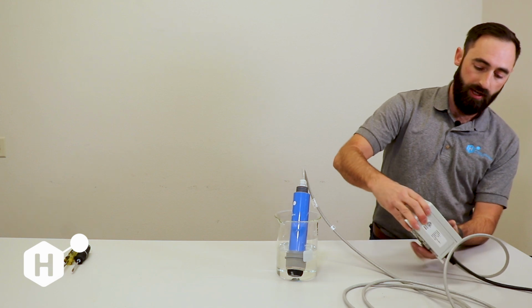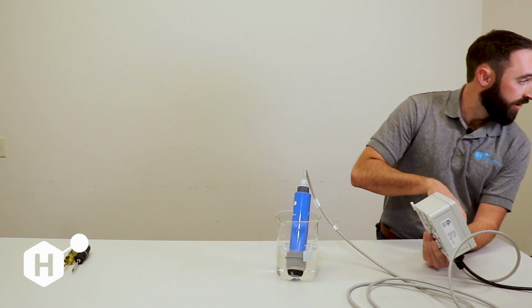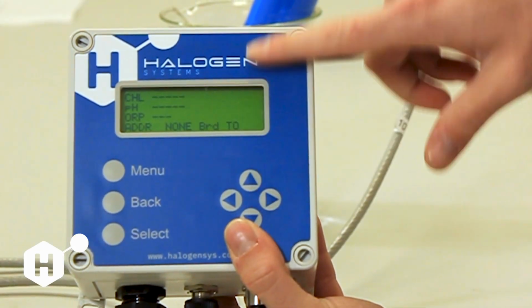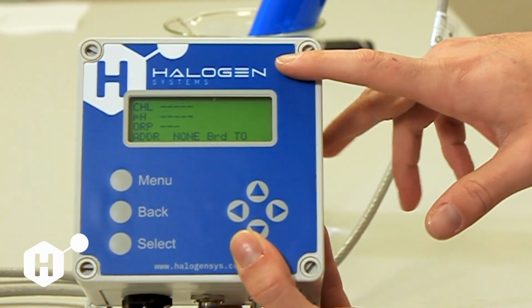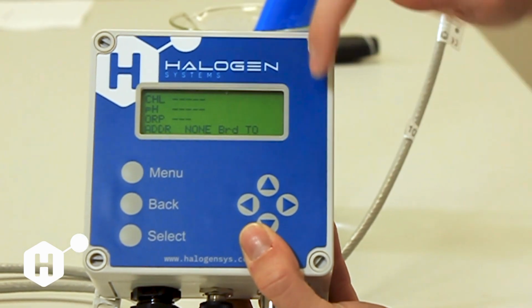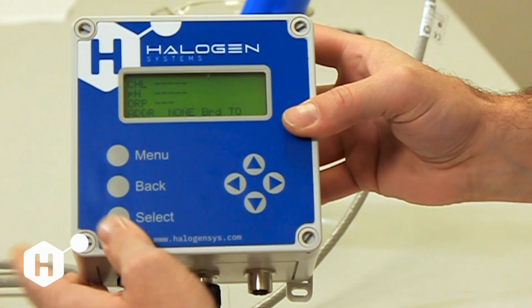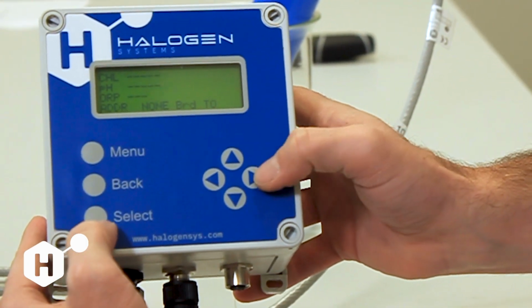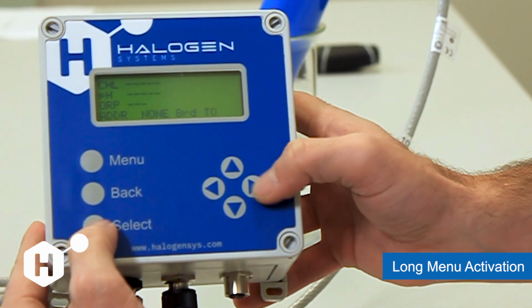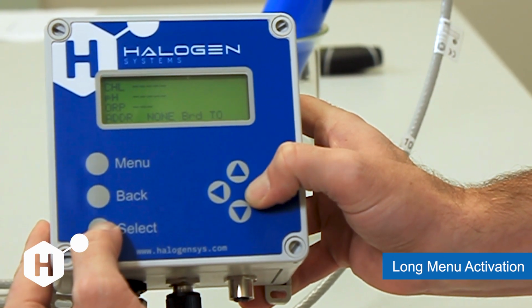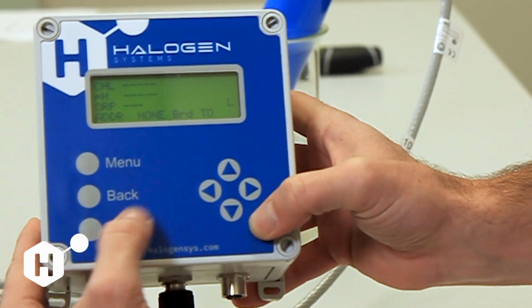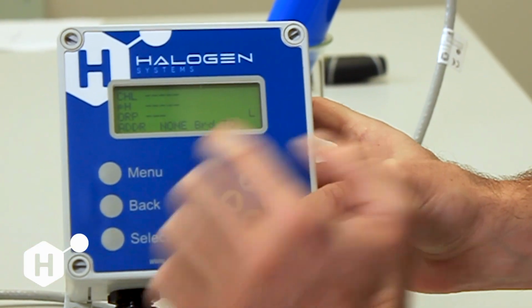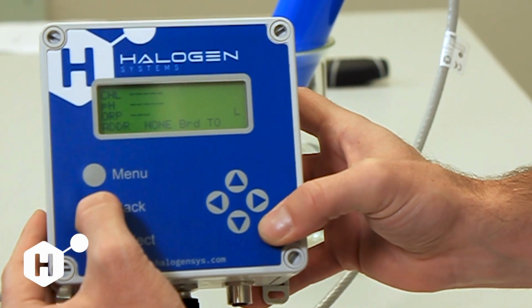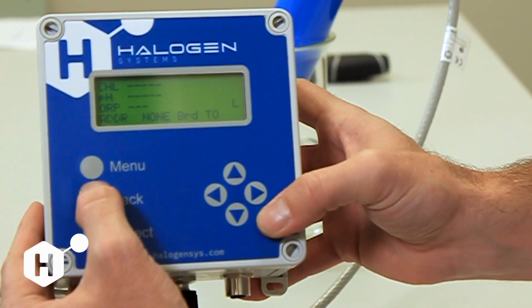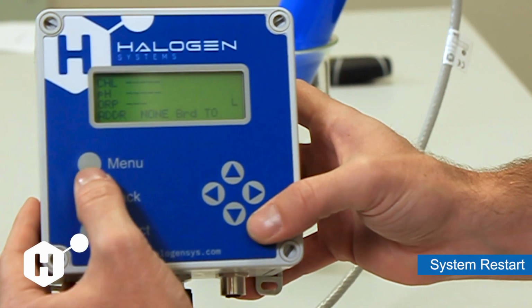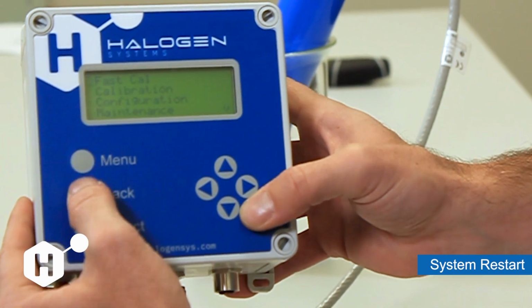Next, I'm going to come over here to the display. I already had power to the display. When you first power on the display, it's only going to cycle and look for COM addresses for the first 45 seconds that it's powered. After that, it's not going to be searching anymore. To initiate a search without unplugging the sensor, you can activate the long menu by pressing select and right arrow together for 3 seconds. You're going to see the long menu selected pop up on the screen. You're also going to know because there's an L over here in the right-hand corner. There are two ways we can do this. We can either restart the system, or we can do a clear errors command, or we can do a Modbus search as well.